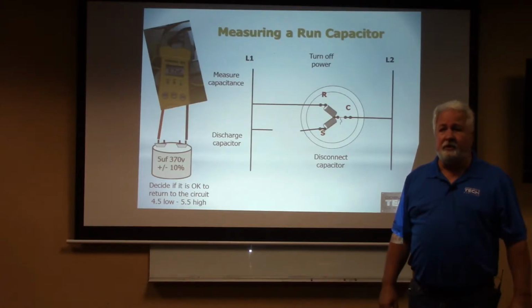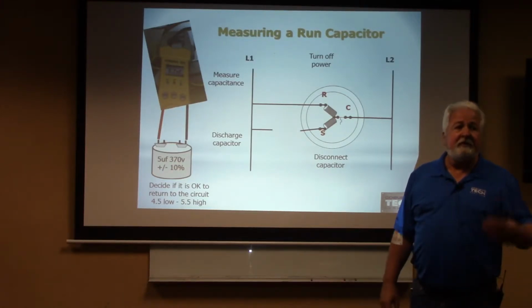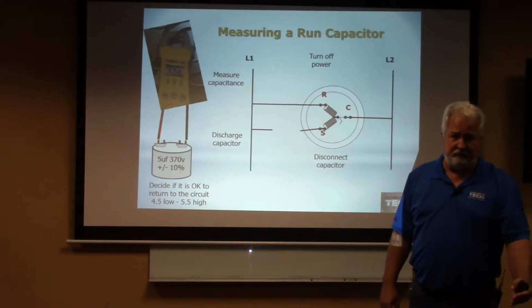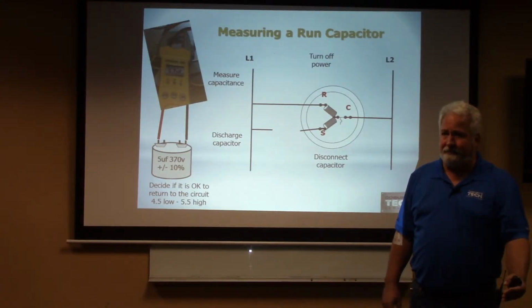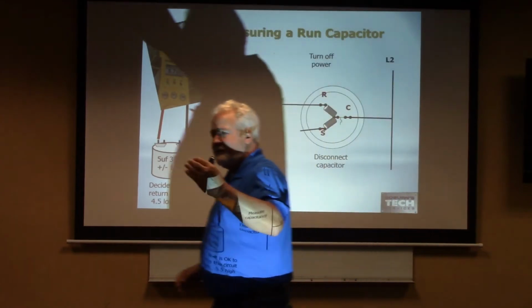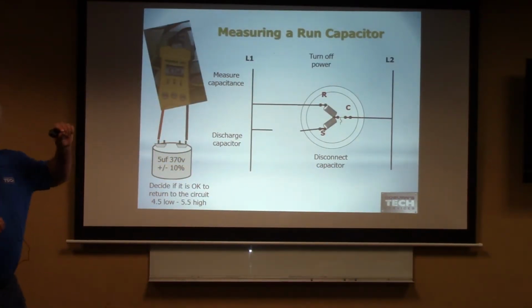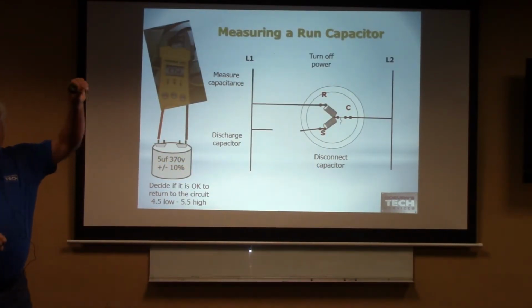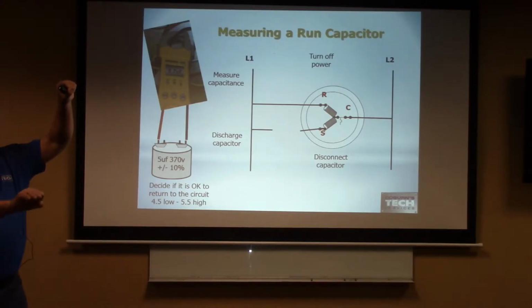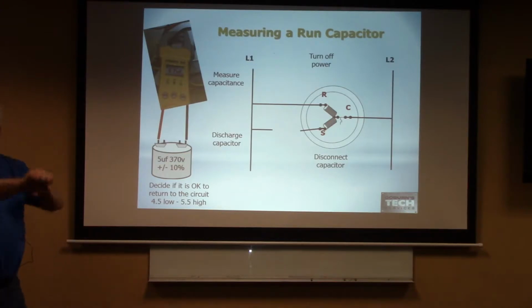Good. So we're going to need to be able to explain to that customer that it's out of tolerance. Does that make sense? It's not bad. It's out of tolerance. What we did when we did this is, remember our pedals on our bicycle? We had one here and one here. Is that right? What you did when you throw your capacitor out of tolerance is you move that bottom pedal to here. It's not here anymore where it's doing this. It's here now where you're kind of doing this. It's operating, but it's not operating efficiently anymore.